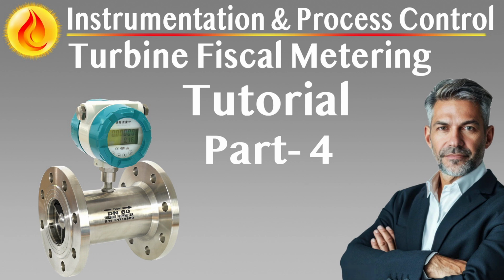Each release of the Fiscal application software must be assigned a unique version number, visible both on the system display and on printed reports. Installation of new software or firmware must be traceable, including the name of the person performing the update, the date and time, and the reason for the change. Any modified configuration parameter must be recorded with both its as found and as left values to ensure full transparency and reversibility.